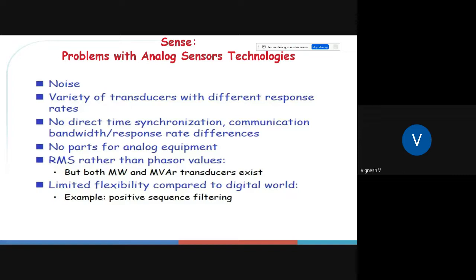So why do we have to go for PMU? What is wrong with existing SCADA and analog technologies? If you ask me, there are lots of noise in analog based technologies, and there is no way to filter them. Another important disadvantage is that it gives you just the RMS value and not the phasor value. So can anyone say what is the difference between getting just the RMS value versus the phasor value? What is the major difference? Can anyone say?